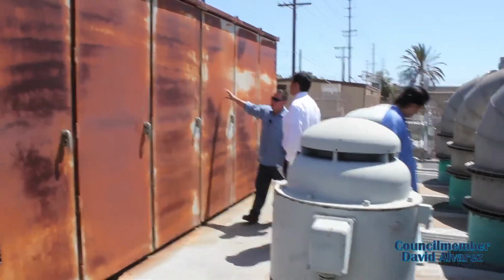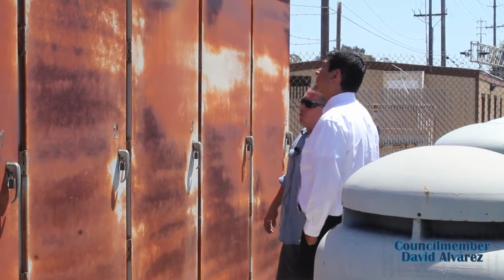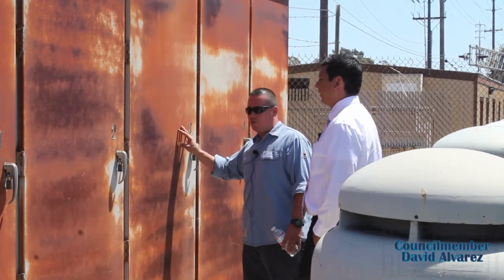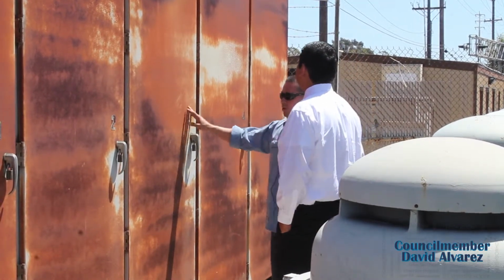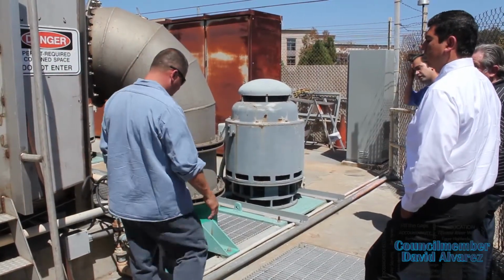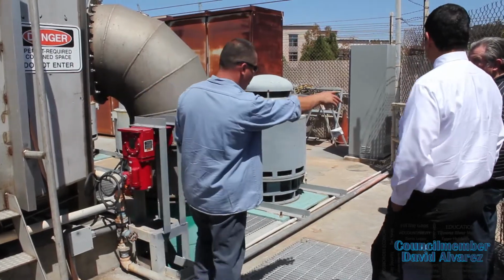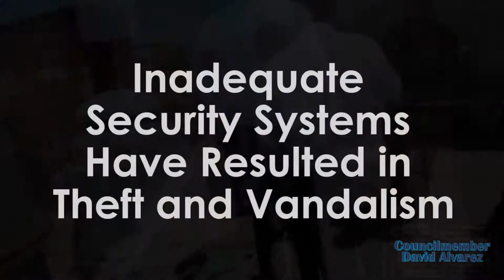Basically, the gear. This is high voltage gear. Okay, the outside, as you can see, it was part of the report from the URS that it's heavily corroded, needs to be actually just fixed, and we haven't done really anything to prevent the corrosion. And as you see, this is old galvanized pipe. It looks good from here, but once we get into the outside there, where you see the blue spray paints, those are all bandages. Those are all just quick repairs.